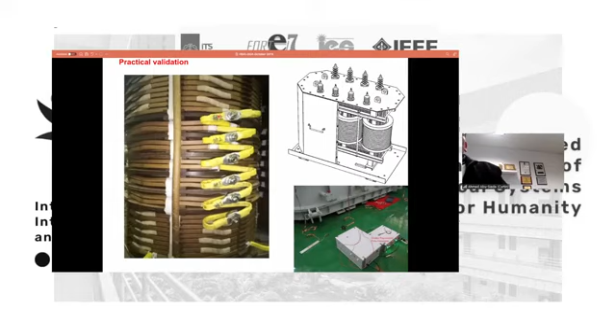But again, the question is how we implement this in real time. We can measure the voltage through a capacitor coupling sensor and the current through a Rogowski coil. But the issue is that an operator like PLN in Indonesia may not allow you to inject a voltage of 500 volts or 1 kilovolt into their operating transformer, even if it's only for a few microseconds—they would be reluctant. So the feasibility of this technique is still in question.